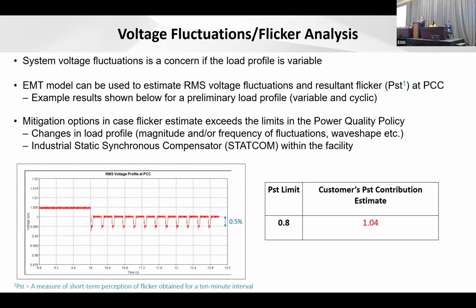So what do we do? We take these analysis results and share them with the customer. This data center customer can actually do things within the facility—they can stagger their operation, change the magnitude and frequency of these active power variations, and even the wave shape. Instead of a step change, for example, it can be a ramp change. Things of that nature can bring flicker down within acceptable levels.